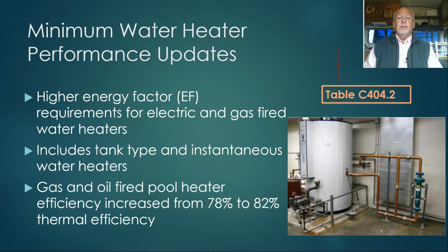Energy factor is a method of determining the energy efficiency of a hot water heating system. It includes not only efficiency of the fuel source or the heating type, but also standby losses, for example, in tank-fired systems. The new standards do include both tank type and instantaneous water heaters, so if you're specifying or reviewing tankless water heaters, there have also been updates to those energy factors. And then finally, worth noting is that gas and oil-fired pool heating equipment efficiency has increased from 78% to 82% thermal efficiency.